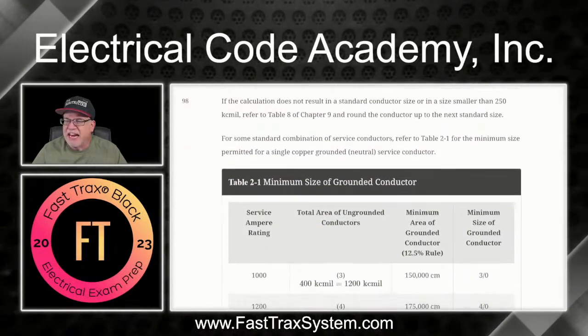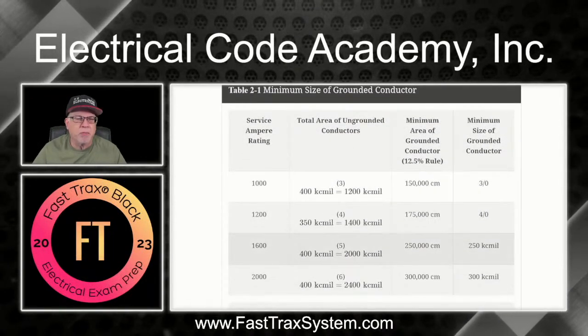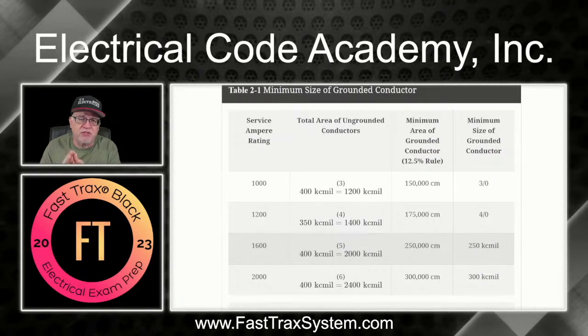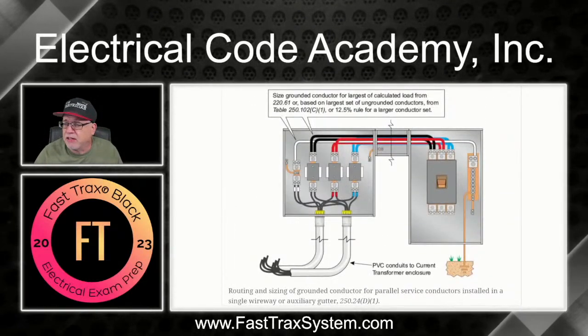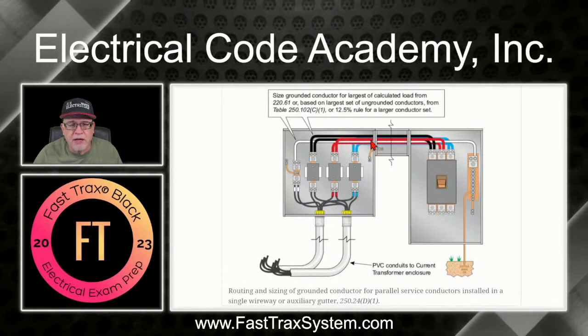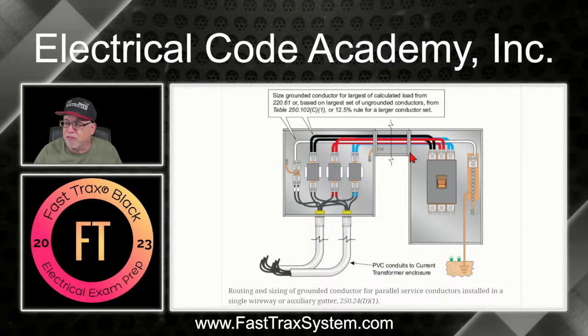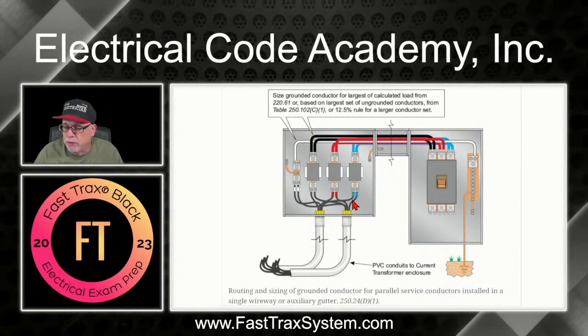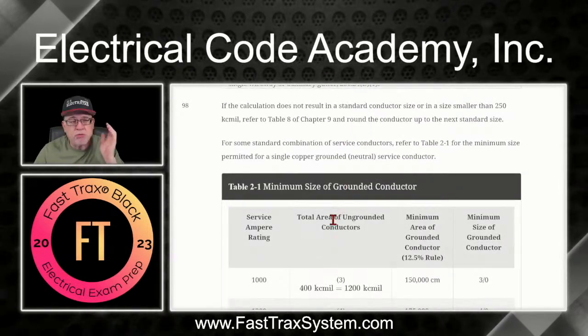All right, now for some standard values, so you don't have to do the brain surgery, if you want to commit things to memory, because they are very consistent. The example we're looking at on the screen is still one raceway. This could be one EMT, or one rigid conduit. Right here it's showing a wireway or extra wiring space, like a gutter. This is all one space, so this is all considered one raceway. That's what we're still looking at here.